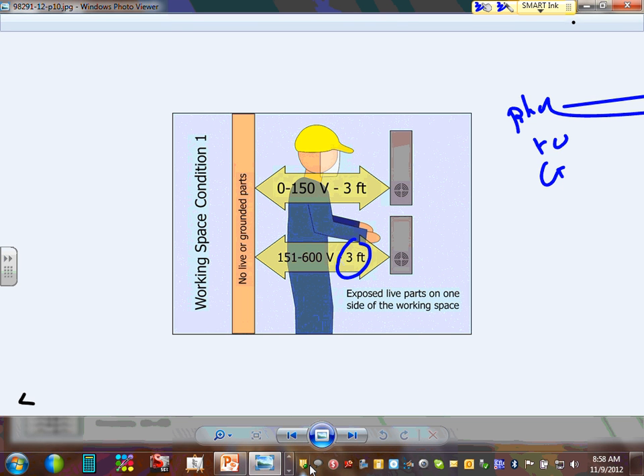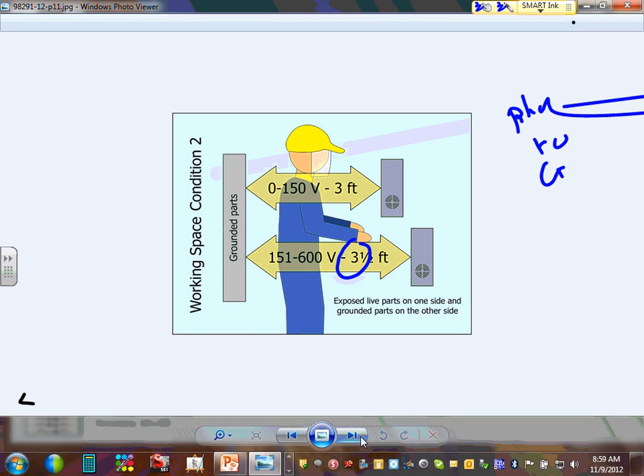If that panel was 208, 480/277, then I still need 3 feet. Can I have everybody understand what condition 1 is? Sheetrock wall, right there. Sheetrock wall. Look at condition 2. When you go to condition 2, guys, really nice. That's what I like about these pictures, because it's better than everything.